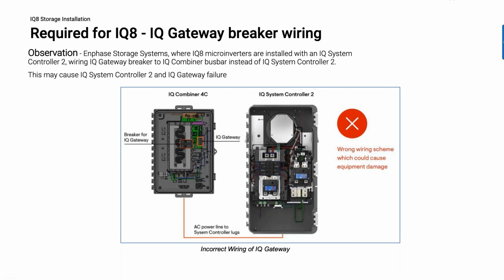Now, the little caveat here is that there are circumstances where the gateway actually signals this relay to close, right? So if this gateway signals this relay to close, if the gateway is on this side, it'll never get power. So if it never gets power, it can't signal the relay to close. So there's this catch-22 here, right? So the way that you have to solve this is you put the power to the gateway on this bus. So the gateway is always powered when this bus is powered. And then this gateway can signal the relays to close, connecting the AC through, right?